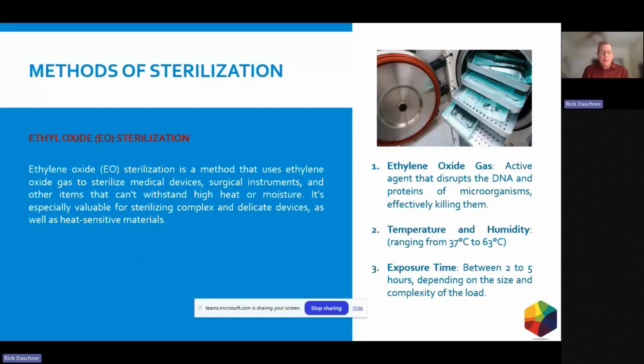Ethylene oxide sterilization. Ethylene oxide has come under fire lately for its damage to the environment and concerns of communities that have ethylene oxide processing plants and usage nearby. So it's a great way to sterilize, but it has come under fire a little bit. So keep that in mind. But it's still used widely. So EO sterilization is a method that uses ethylene oxide gas to sterilize medical devices, surgical instruments, and other items that can't withstand high heat and moisture. It's especially valuable for sterilizing complex and delicate devices, as well as heat-sensitive materials.